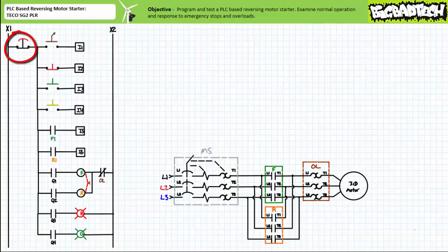Note the maintained contact normally closed e-stop is not a direct input to the PLC, but rather serves as a hardwired bottleneck through which all six field input devices immediately downstream of it must negotiate to issue input to the PLC. Wired in this fashion, the hardwired e-stop effectively severs all incoming communication with the outside world without the necessity of resorting to any programmed instructions to do so.